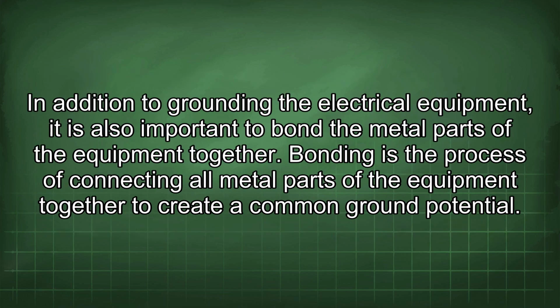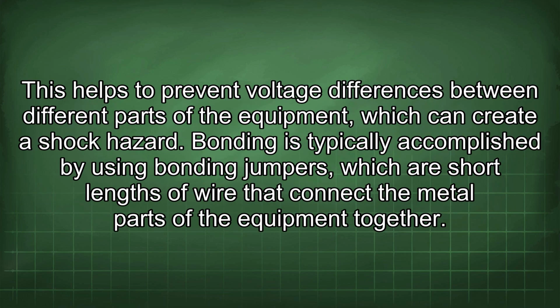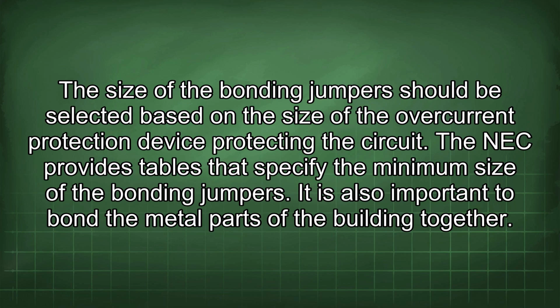In addition to grounding the electrical equipment, it is also important to bond the metal parts of the equipment together. Bonding is the process of connecting all metal parts of the equipment together to create a common ground potential. This helps to prevent voltage differences between different parts of the equipment, which can create a shock hazard. Bonding is typically accomplished by using bonding jumpers, which are short lengths of wire that connect the metal parts of the equipment together. The size of the bonding jumper should be selected based on the size of the overcurrent protection device protecting the circuit. The NEC provides tables that specify the minimum size of the bonding jumpers.